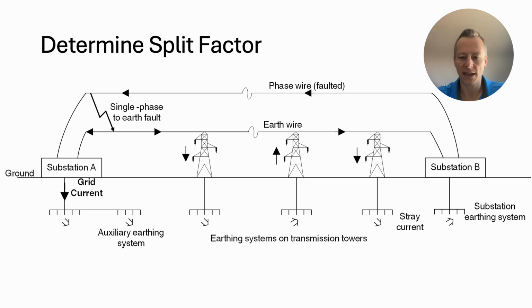So the next topic is split factor. Basically the concept comes down to this. Your GPR event, ground potential rise, is entirely tied to how much fault current is going from the grid into the earth. So if you've got transmission static wires that are grounded as well, some of that fault current will return to the source on that static wire. Some of it will also leave on distribution feeders that leave your station and go out. They have a neutral wire that gets grounded periodically on every pole.